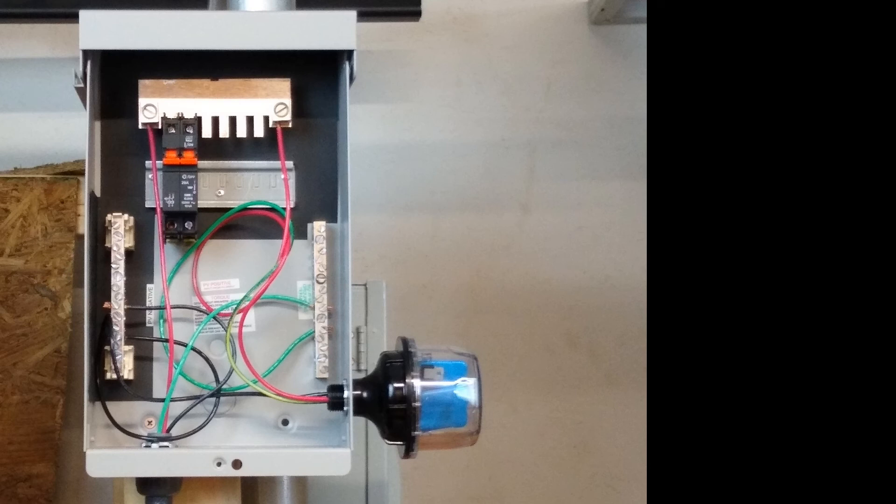And you can see on this particular example, the tab has two lugs attached. So we're using one of the lugs for the positive PV output circuit, and we're using the other lug to connect in our surge protector. So that's it for wiring a MidNite Solar DC combiner box.